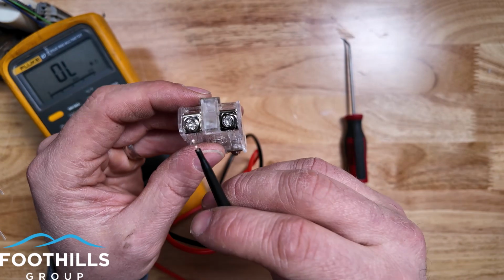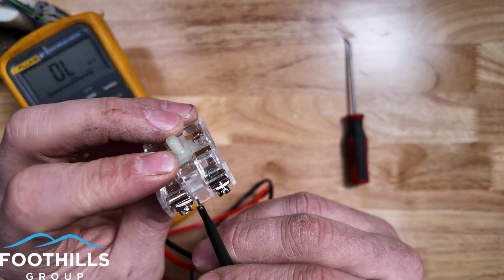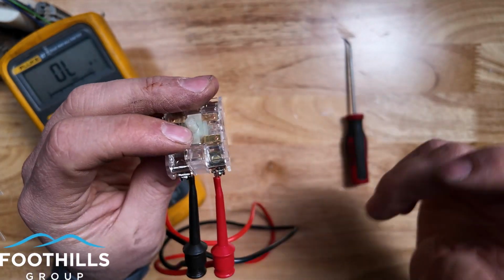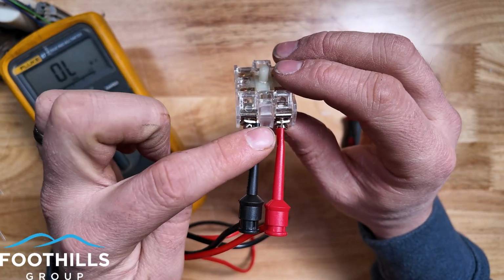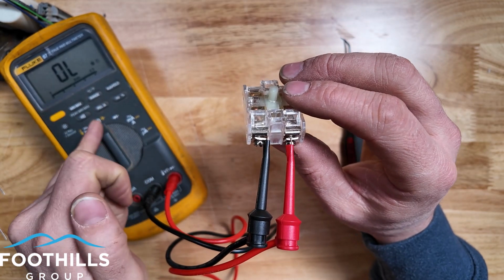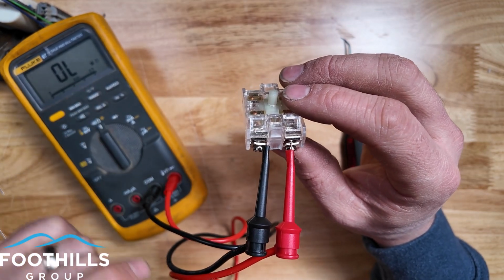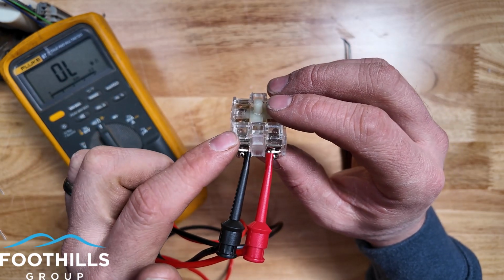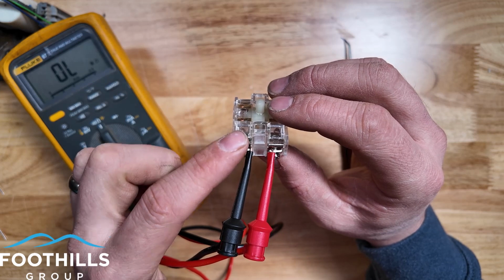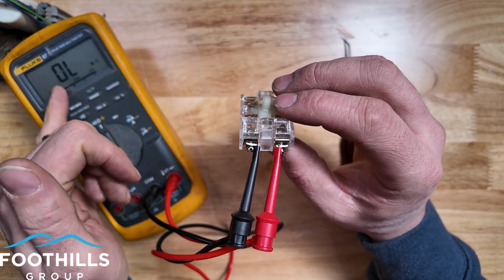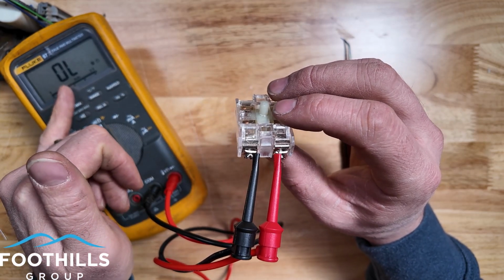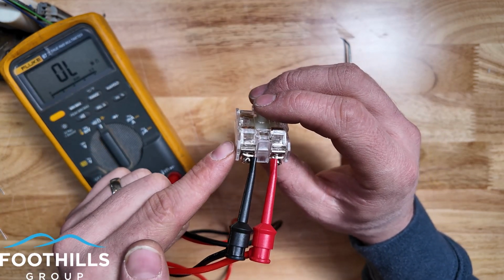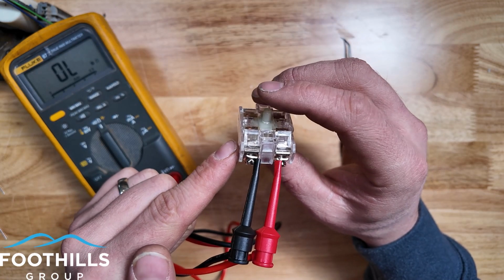Right now, if we hook up our meter leads, we can see what the electrical state is. There we go. So we hooked up our meter positive, negative. We have our multimeter on ohms, and we have our meter auto ranging. Auto ranging is helpful when doing switches because you will go from out of limits, infinite resistance, millions of ohms essentially, but beyond measurable for your meter, that's an air gap resistance, all the way to 0 ohms, which is perfect continuity, which is what we'd expect when we operate the switch.